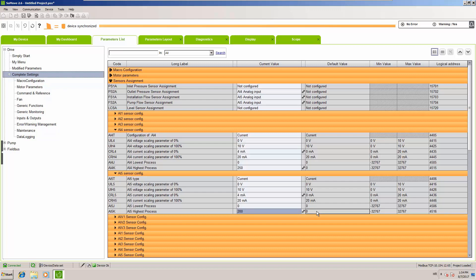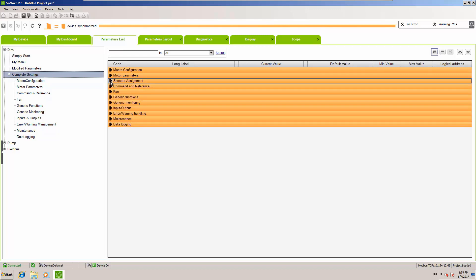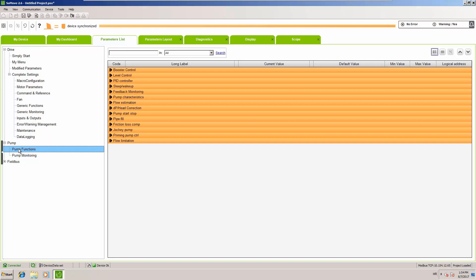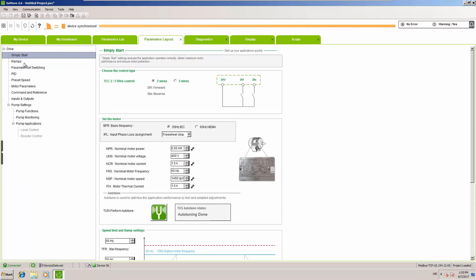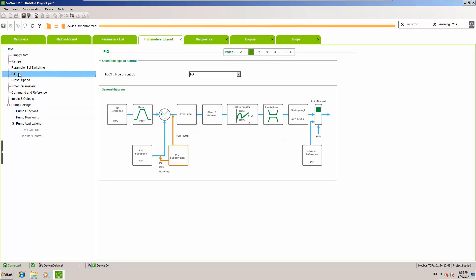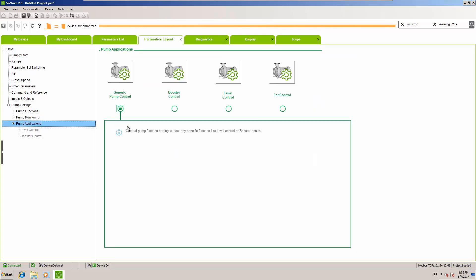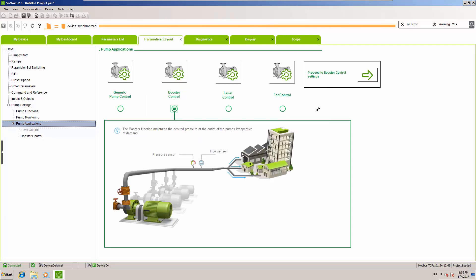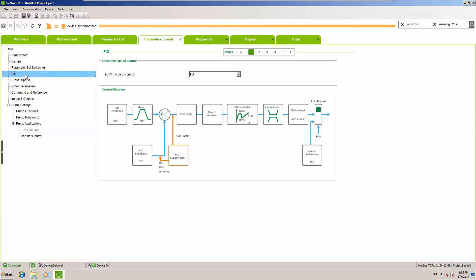Now that sensors are set, we can configure our PID function. At this point you can also choose the application type. We said it is going to be a booster station — for pure PID it doesn't have to be a booster station, since booster automatically implies a multi-pump system. You can leave it as generic pump control or select booster. At this moment we will not enter complete booster settings — we will only do PID.